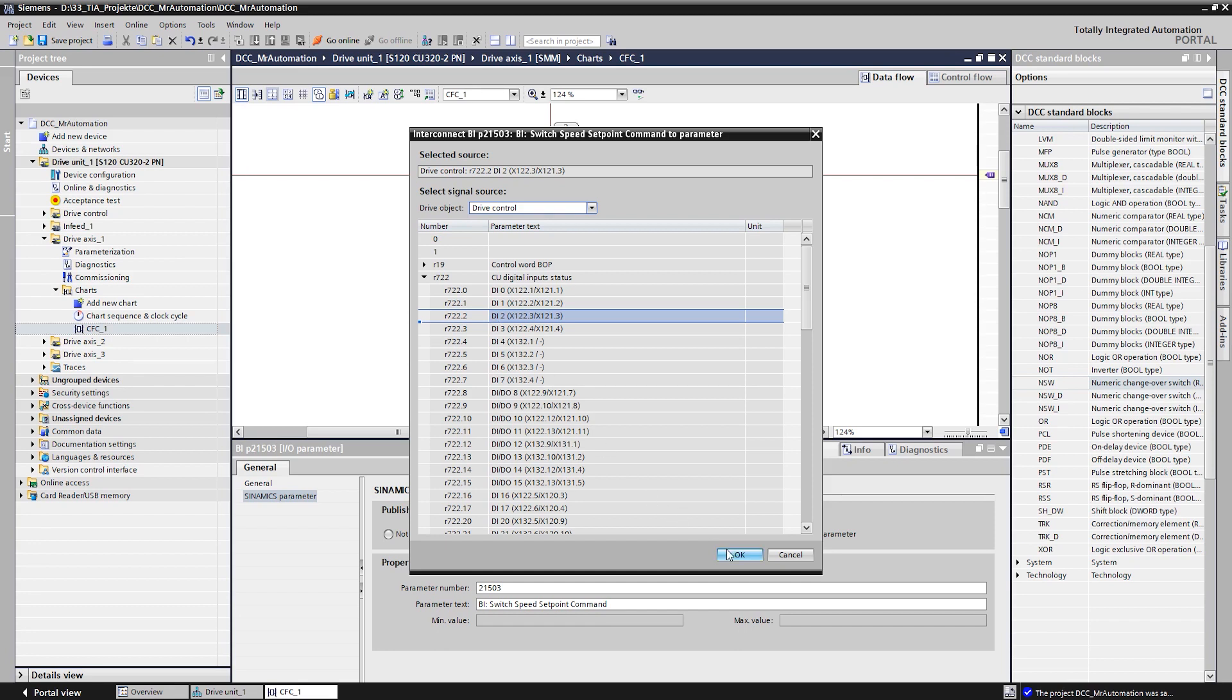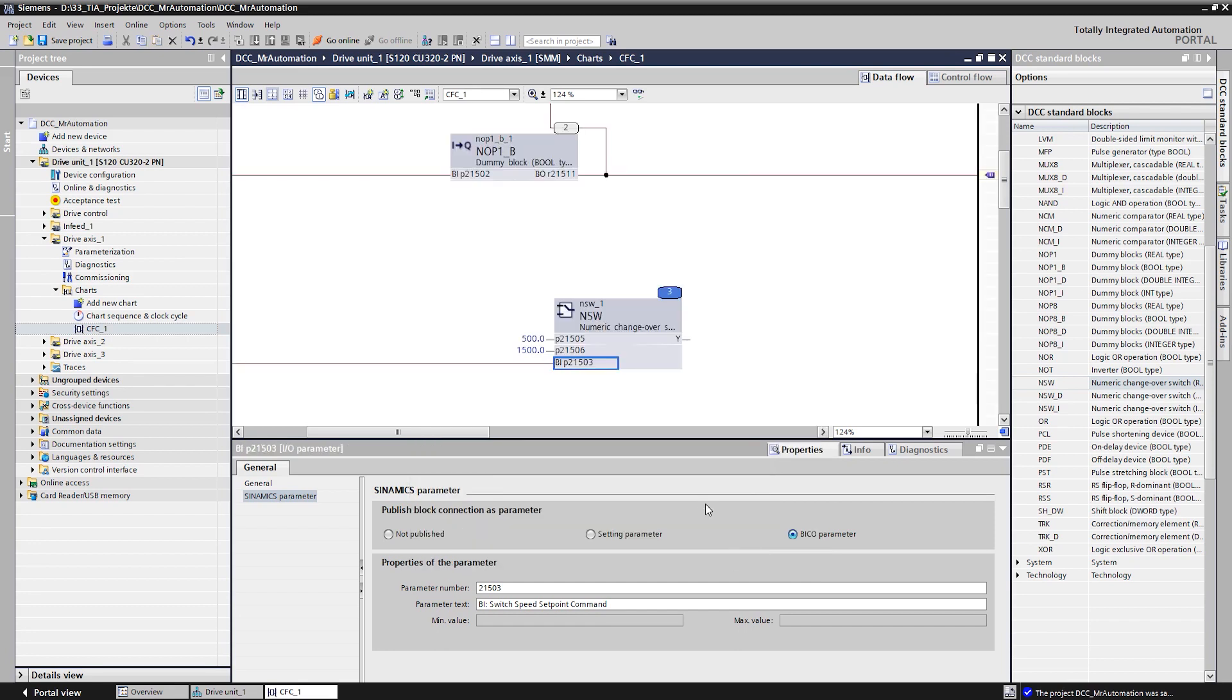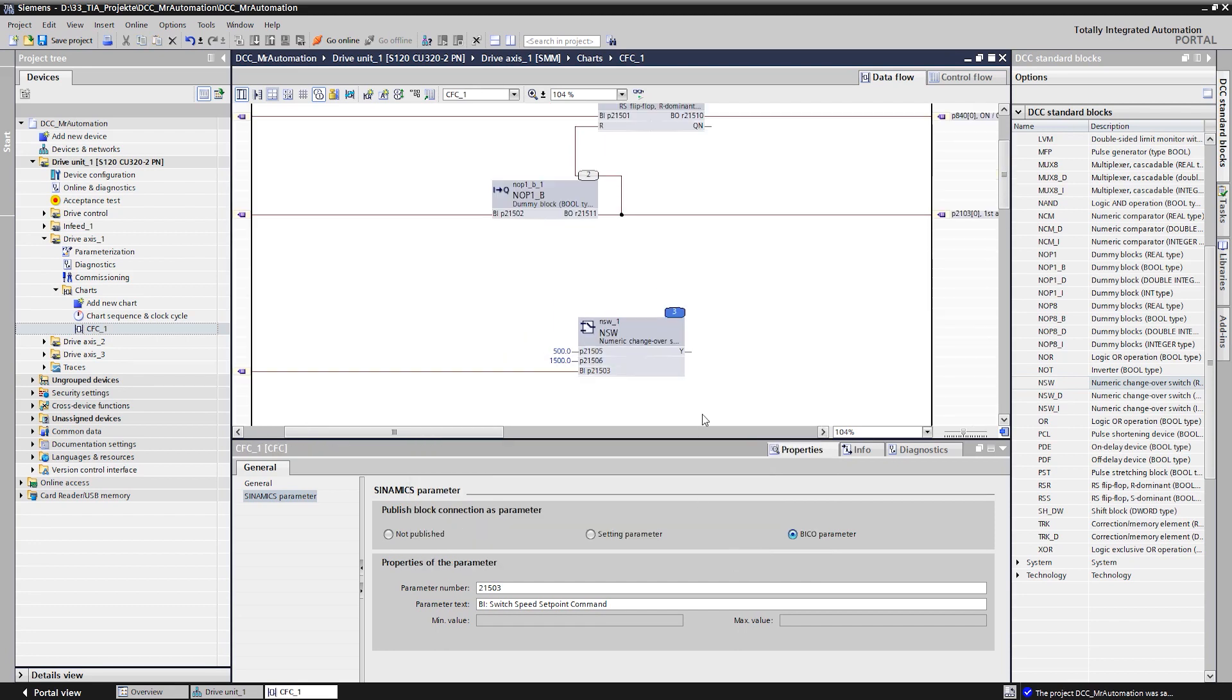The last step is the transfer of our speed reference values to the speed controller of the basic system. For this, it is important to mention that all reference value signals are transferred in Sinamics as percentage related values. In order to convert our absolute speed values into the corresponding related value, we read in the reference value, divide the absolute value by this reference value and obtain the appropriate percentage reference value.